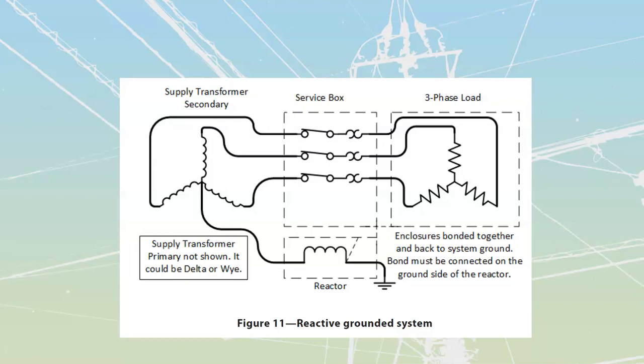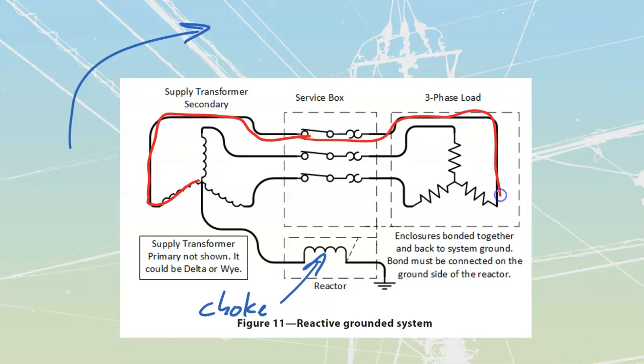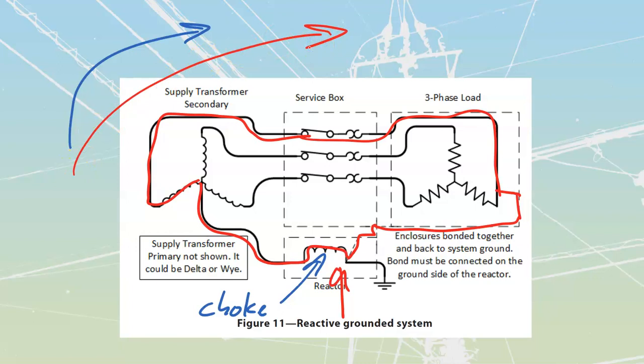It does limit things as well—going back to some earlier years, second year we looked at tau, the rise of voltage across an inductor or reactor, sometimes called chokes because of their slowing down effect. This will still allow a large value of fault current, 50 to 70% of unrestricted, but that 50 to 70% that would happen is going to get slowed down. So the overall current rises slower, meaning we won't have as violent an explosion, nor as much arc flash incident energy dissipated immediately.